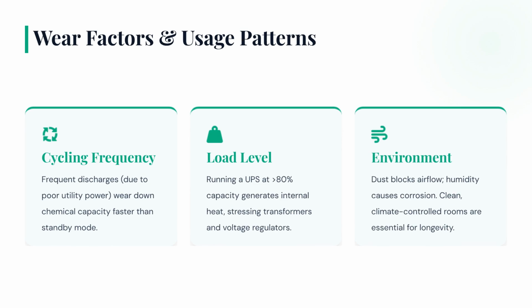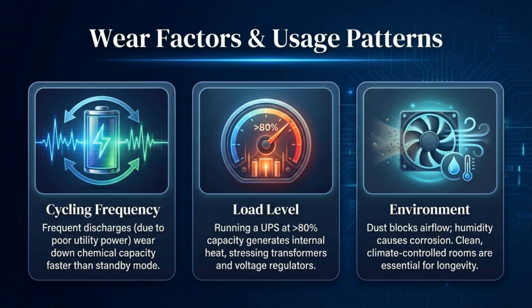Frequent discharges or cycling wear down capacity faster than standby mode. Operating the UPS above 80% capacity generates internal heat. Finally, dust and humidity in the environment cause corrosion and block airflow. Controlling cycling frequency, managing the load level, and maintaining a clean environment are essential for extending the longevity of your system.